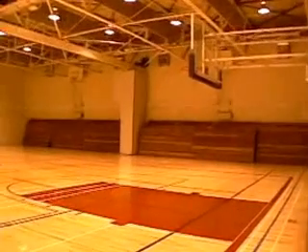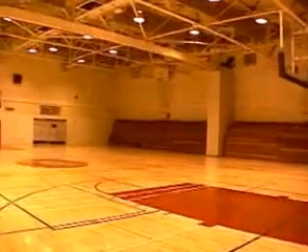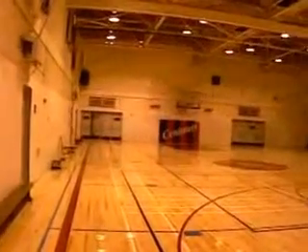Here in our district, we've had a common problem in most elementary gyms that get low usage. They've got constant volume air handling systems, gas fired. These turn out to be very expensive. And if you're running a gymnasium for 300 people, it doesn't need the same amount of outdoor air when you're only operating with 30 people in a gymnasium class or a phys ed class.